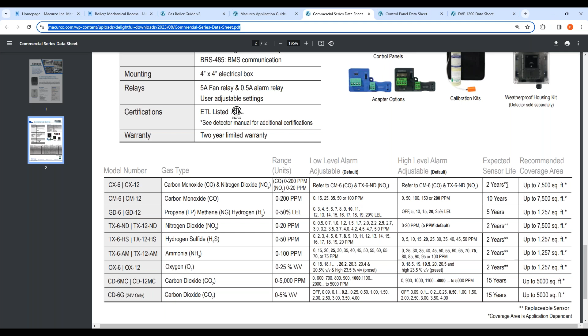Going back to the types of systems real quick. From the detector standpoint, the easiest way to talk about these pages is you can eliminate the fan photo, the horn strobe photo, for anything you want that can be controlled or signaled. So you could take that horn strobe and substitute it for a fire security panel, a BMS, a SCADA system, a fan, a valve, a damper, etc.